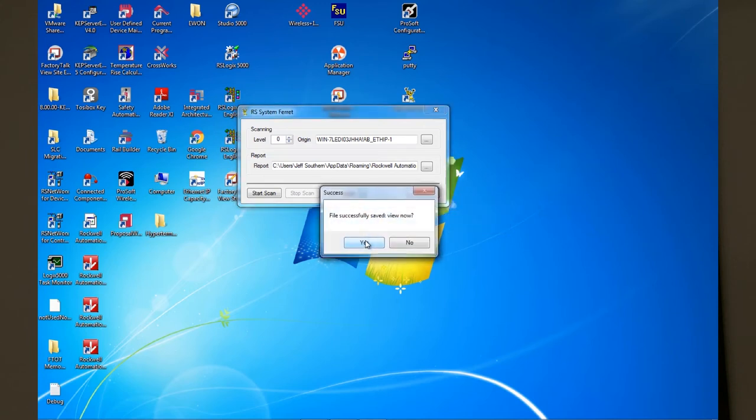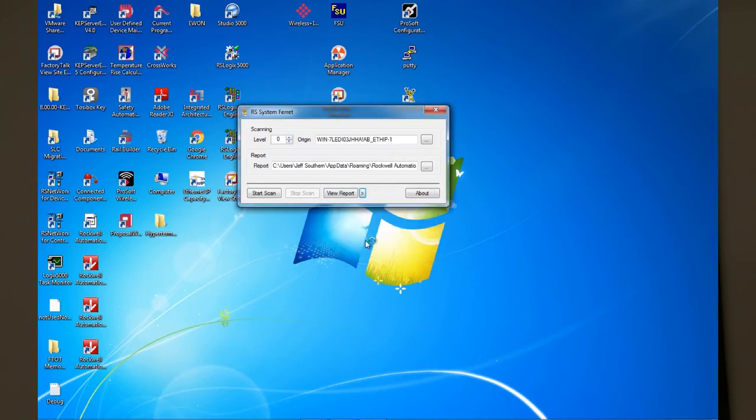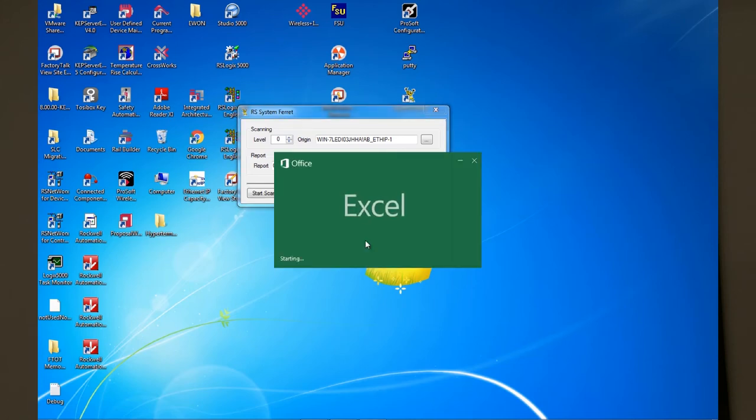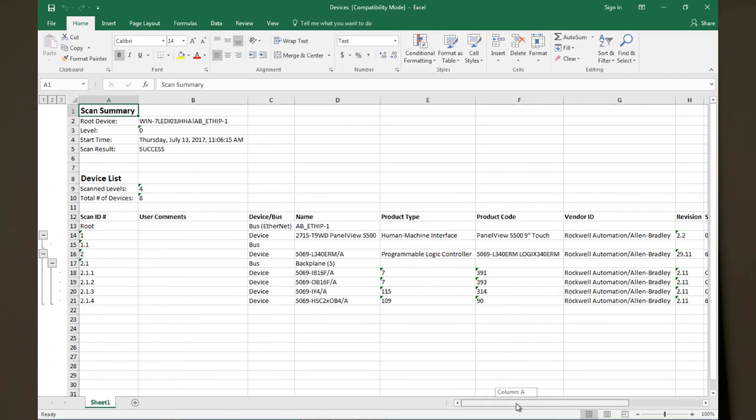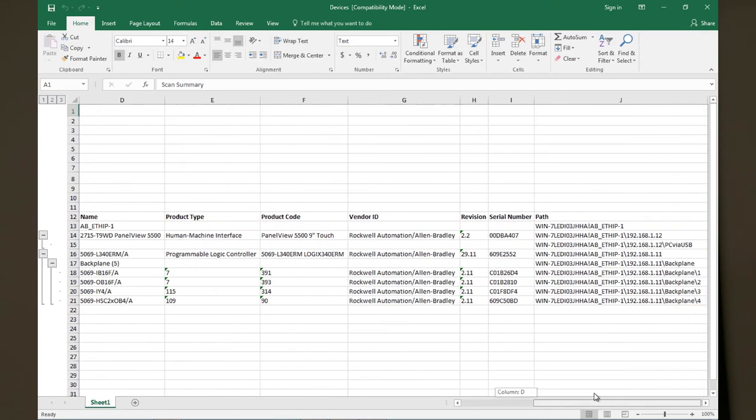Once the conversion is complete you can view the file and you get some good information about what you've scanned. In this case it shows the product name, the product type, the product code, the vendor ID which is typically going to be Rockwell. It shows you the software and firmware revisions and it shows the serial numbers and even the communication path where the devices were found.